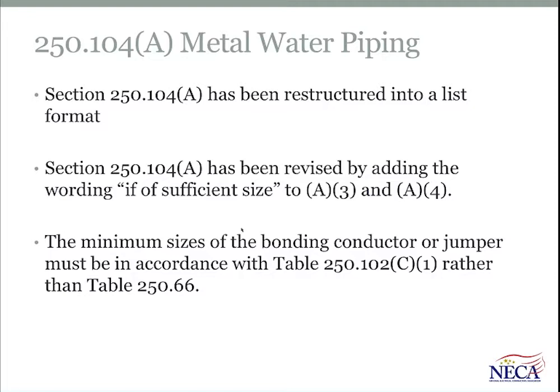250-104A was restructured into a list format to provide a more logical layout, actually, and to clarify by adding some words "if of sufficient size" to A3 and A4. But the big change in this section is the minimum size requirements for a bonding conductor or jumper for metal water piping or structural metal framing member.